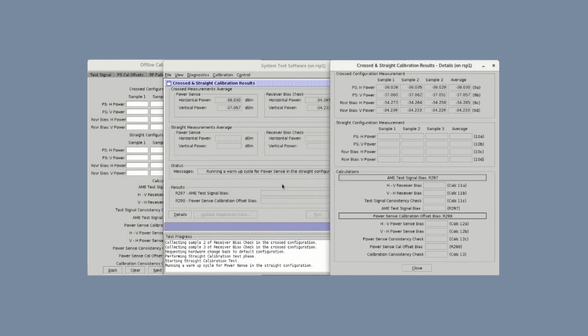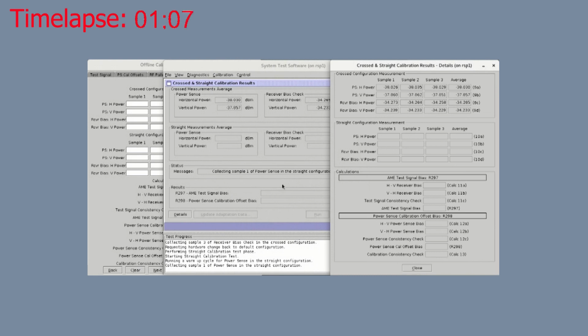As the calibration routine populates the power sense horizontal and vertical power and receiver bias horizontal and vertical power sample fields, ensure the samples meet the expected power level and are within tolerance. Power sense measurements should be greater than -40 dB and within 0.05 dB of the previous measurement. Receiver bias measurements should be greater than -36 dB and within 0.02 dB of the previous measurement. Wait for the calibration to complete. The calibration routine runs for approximately 10 minutes.